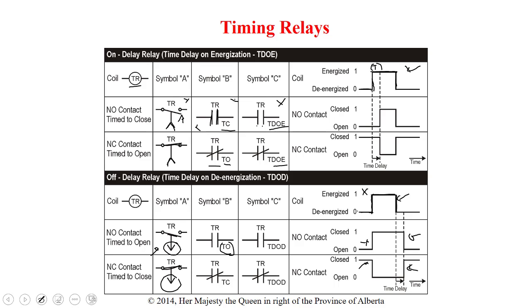There's one other type of contact that's not mentioned on here. A lot of timing relays have IC contacts. So that's an instantaneous contact. They'll respond just like a normal relay contact would: when the coil's energized, they'll change state, and when the coil's de-energized, they'll immediately change state. So you might see a timer contact that says IC. That means instantaneous contact.